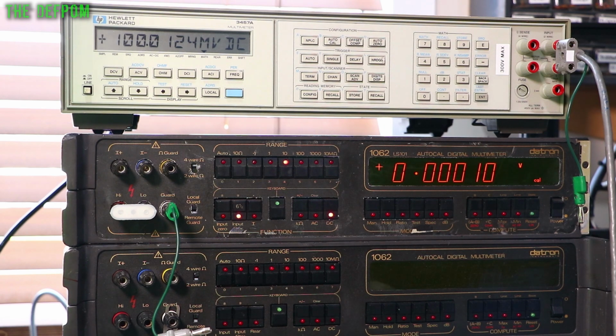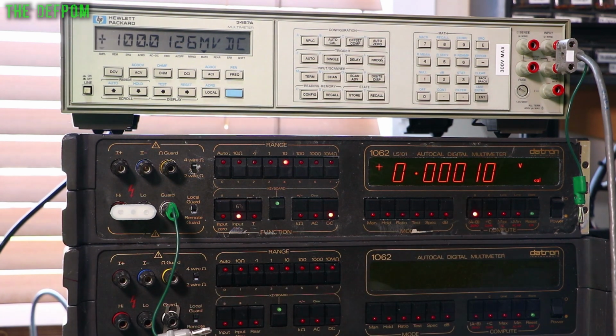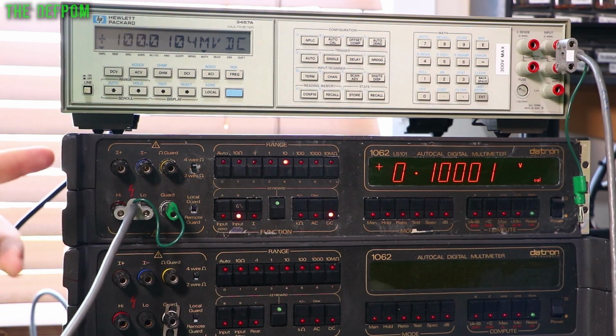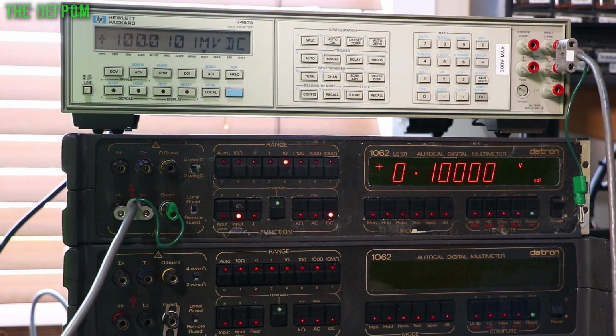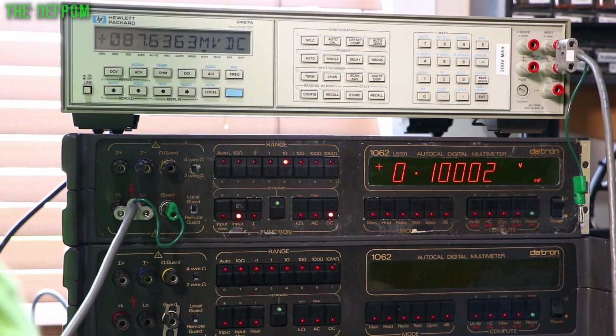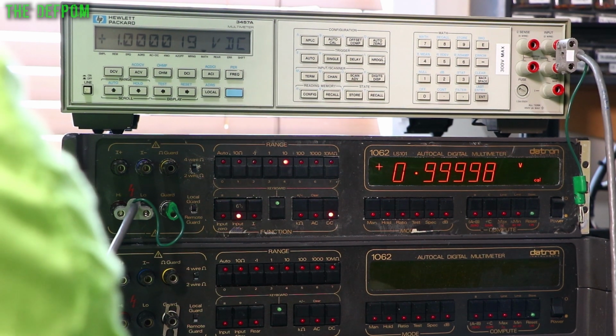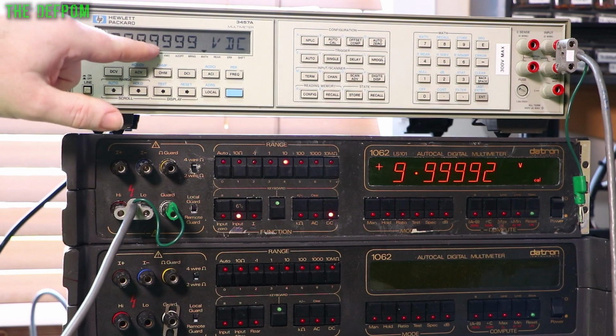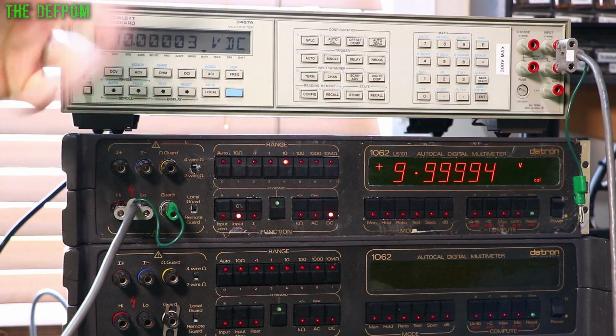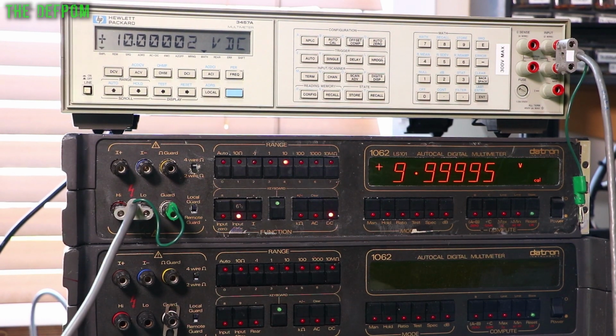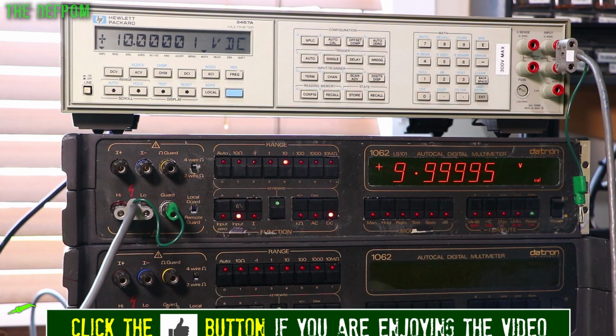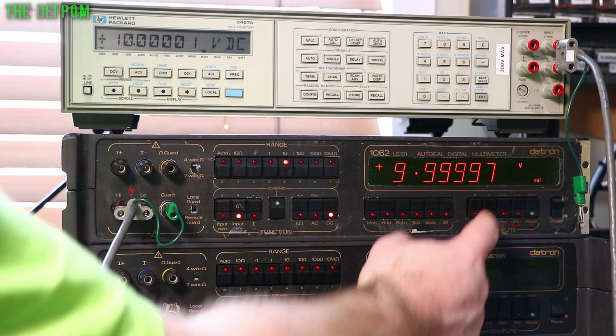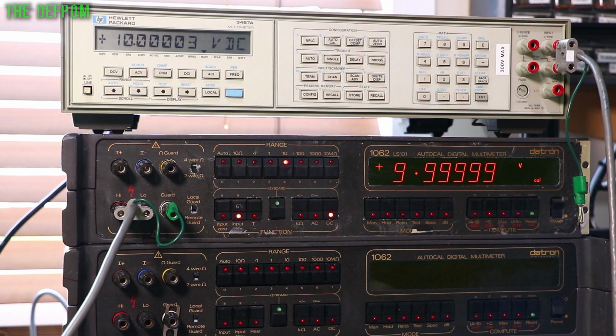Let's do zeroing on 10 volts. So zero button. Sometimes you just do it a couple of times, let it settle, that sort of stuff, but it looks okay. So now I've got to inject 10 volts. As you can see, what I'm doing is 100 millivolts, so I've got to do 10 volts, so I need to change this ranging. 10 volts. Now this says basically 10 volts on here, so I'm just going to say it's 10 volts, you know, within a few counts. You can see this is very slightly different to yesterday. Just a few counts down, you can almost leave it there really, but I'm going to show you anyway. So I'm going to do a gain on that one. That'll set the 10 volt point.